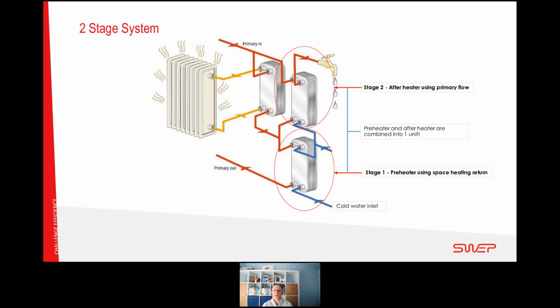With a two-stage system, this is where it gets slightly more complex, so I'll try and go slowly to explain the details. So in the bottom right-hand side is what we call the first stage heat exchanger. And I must put this out at the start, that the two heat exchangers that are circled here are shown separately only for clarity of understanding. It's actually in one heat exchanger, which is another quite nice innovation. You're not having to have multiple heat exchangers on one substation skid. So the first stage, the bottom right heat exchanger, this is what we call the preheater. So cold water's coming in on the bottom right of the heat exchanger, and it's being preheated by the space heating return. You can see that coming in off the heat exchanger at the top left. It's getting a preheat stage as it's going through.